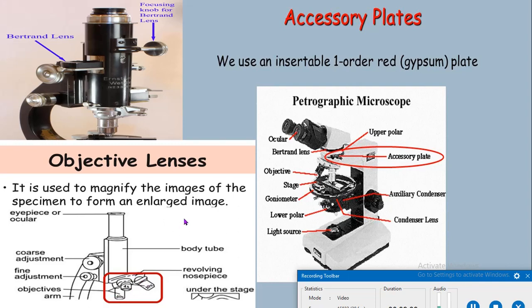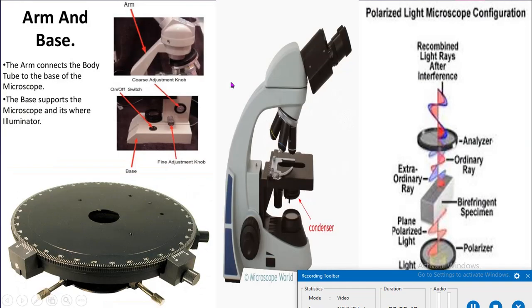The arm and base are the frame of the microscope and function as support in a vertical tube microscope. The arm is normally connected to the base by an inclination joint that allows both the tube and stage to be inclined. In an inclined tube microscope, there is no inclination joint and the arm and base are built as a single frame.